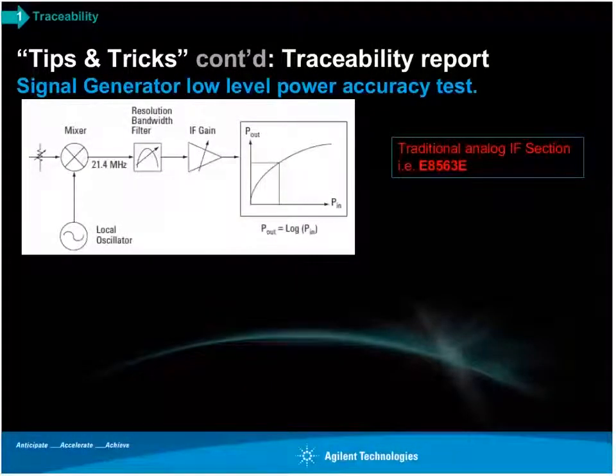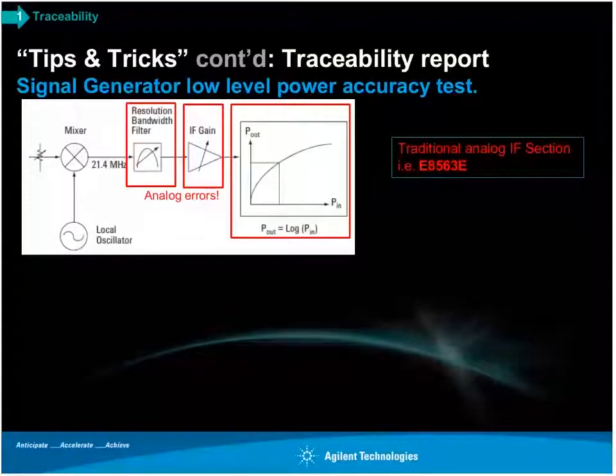Well, zooming in onto that IF section right here, what I want to show you is every time you would switch filters or change the step gain, and one of the real offenders was, in order to get good dynamic range, traditional spectrum analyzers used to have what we call a log amplifier, where the output is logarithmically proportional to the input. These were notorious for errors, over a dB sometimes. So that's a traditional analog IF section.